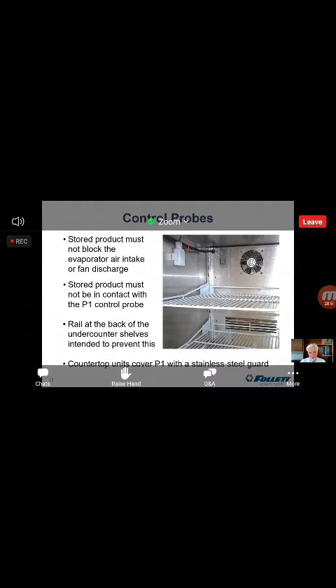And on countertop units, those shelves do not have a rail. So what we have is a little stainless steel guard that clips onto those slots you see right there in the louver, okay? And that protects that probe from contact with the product. If you can't keep the staff from pushing product up against it, even with that rail on an under-counter unit, that guard will work on an under-counter unit. The slots are the same. So you can do that as a last-ditch alternative if you can't keep the staff from pushing product up against that control probe.